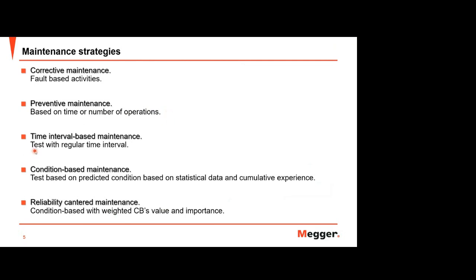And the next strategy is time interval based maintenance. This is testing at regular time intervals. This is commonly used by many customers. They already decide every how many years they do maintenance, to make sure all the systems and all the assets they have are in good condition, and to avoid any sudden failure in the future. This is very common now. Many customers, many people, prefer to use this because they can manage the timing, and estimate any effect after, or when they do maintenance.